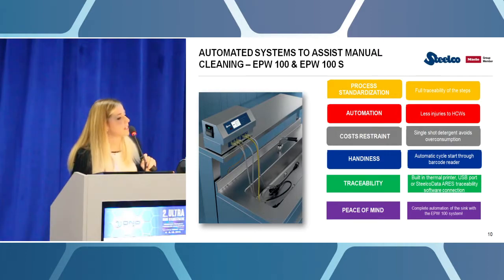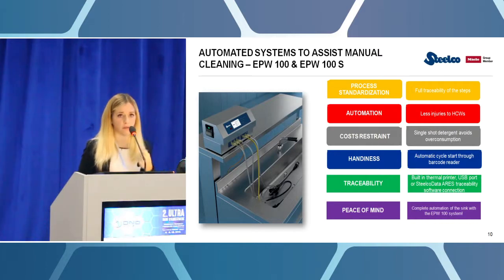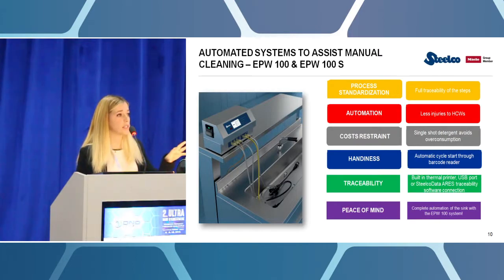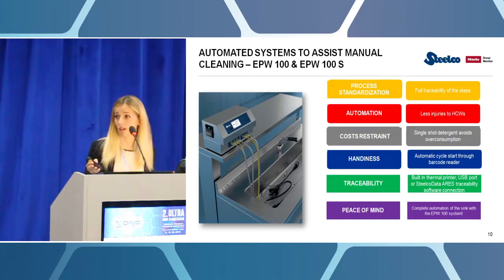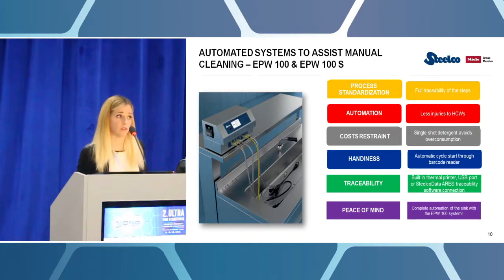As you can see, this EPW 100 basically takes out from the user the activity of leak testing and of flushing, rinsing, and purging the endoscope manually. That is a very strong activity to be made manually. Those who do that every day know how difficult it is to use the syringes and respect the contact time of the detergent to clean the endoscope inside the channels manually. So this machine does all these activities automatically. The only activity that still needs to be done manually for the moment is the mechanical brushing of the channels. But apart from that, the machine does everything else alone.